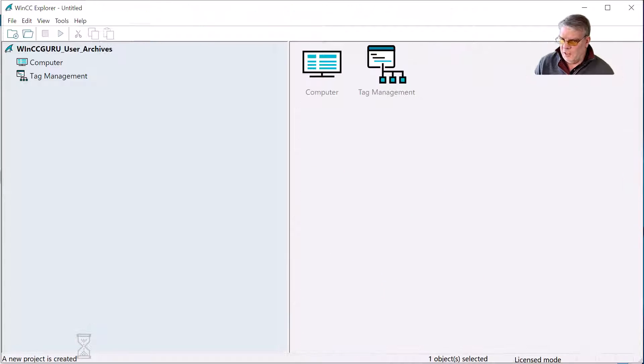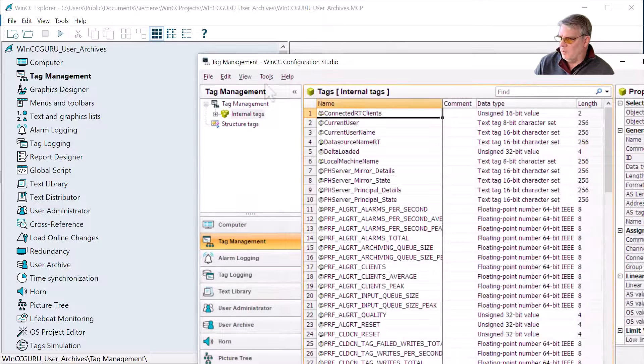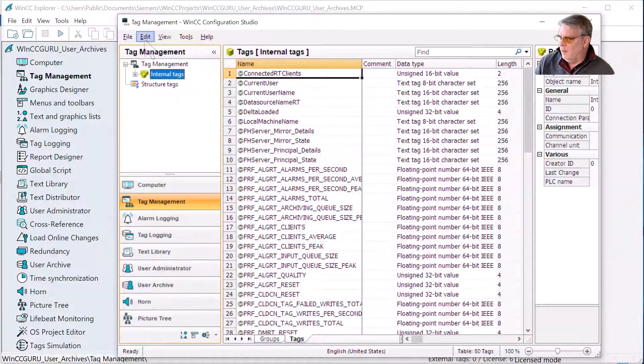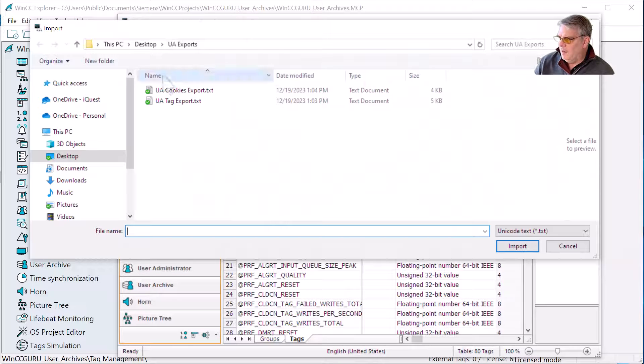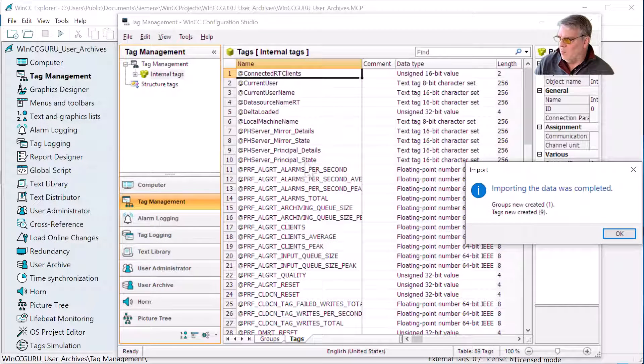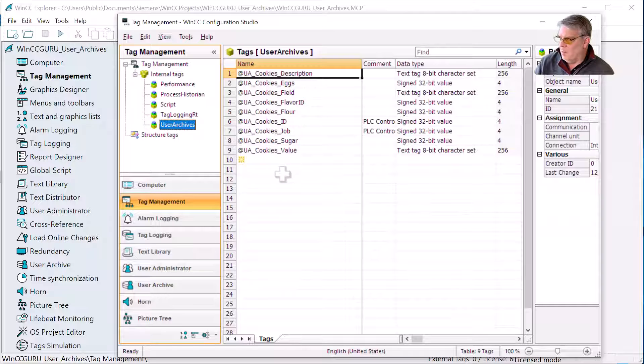It'll close this project and open the new one. We now have our new project. First, I'm going to open Tag Management, highlight internal tags, and under the edit menu I'll do import. There's my UA tag export — I'll hit import. It created a new group with my tags in there. There's my user archive and all my tags. So far so good.